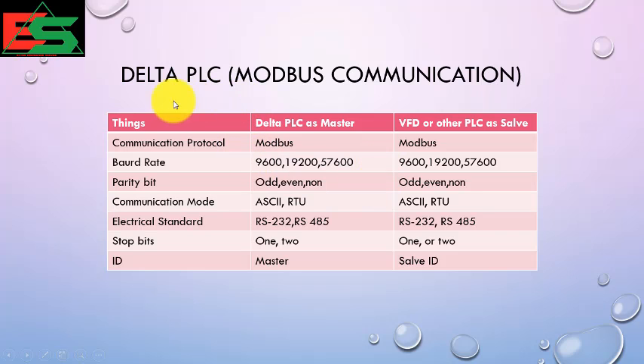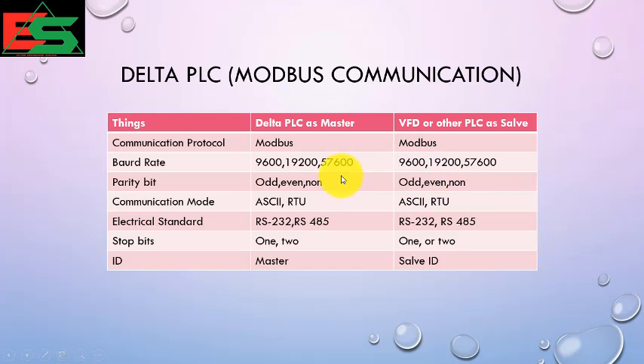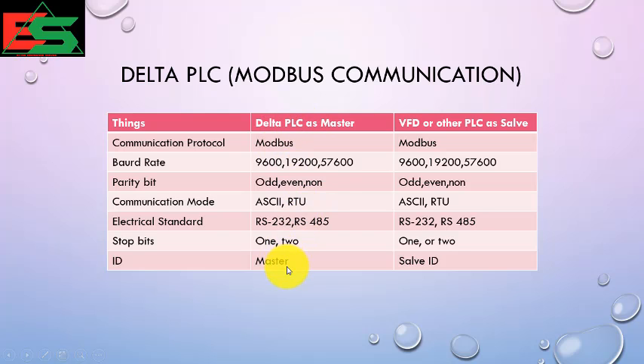Regarding the communication method: Delta PLC acts as master, and VFD or other PLCs act as slaves. Both should be on Modbus communication. The baud rate should be the same on both sides, for example 9600. The parity bit should also match — if you use odd parity in Delta PLC as master, the slave must also use odd parity. The communication mode (ASCII or RTU) and electrical standard should both be the same, stop bits should be the same, and the slave ID should be unique for each slave device.